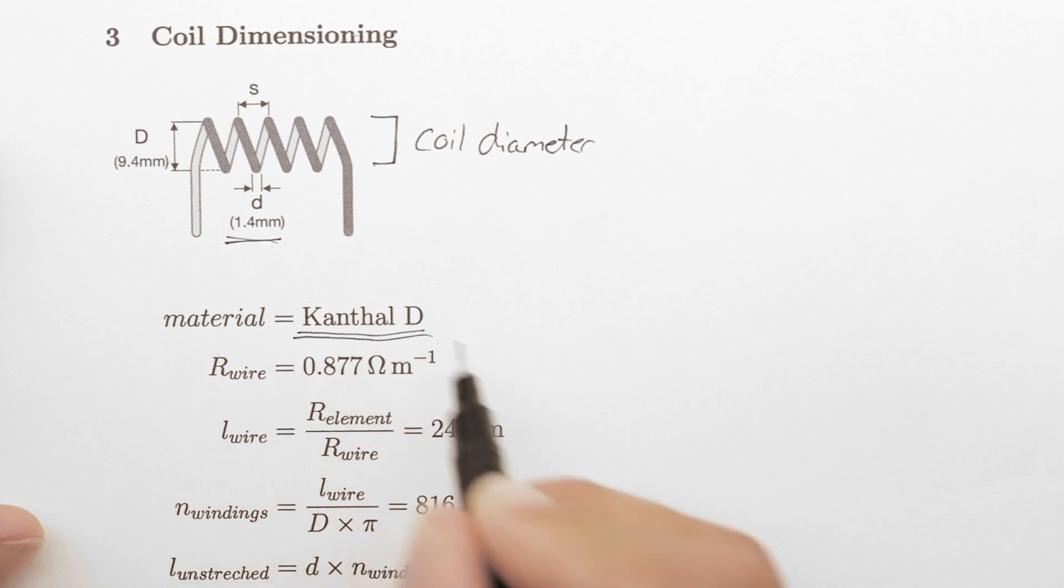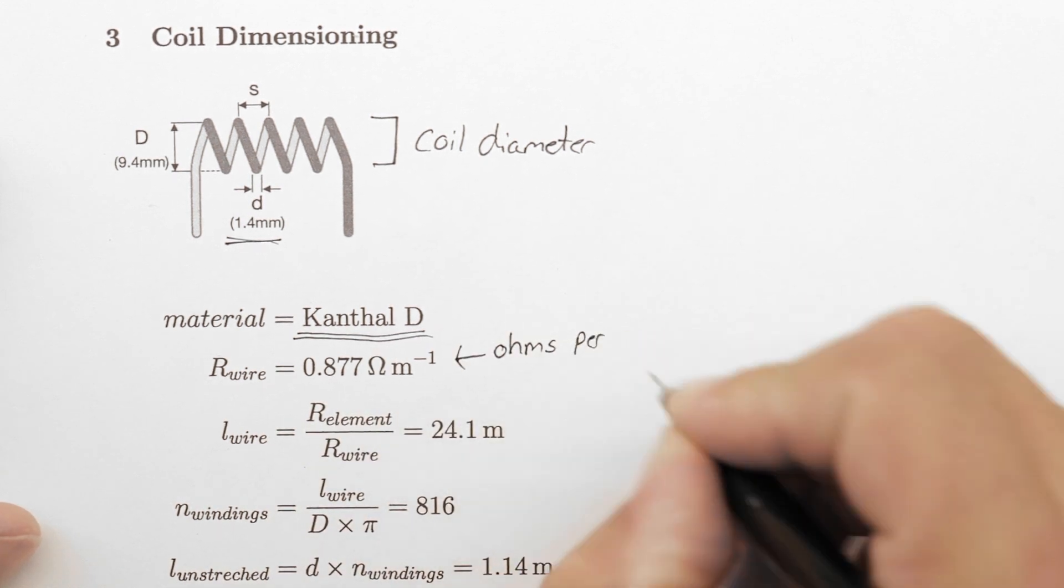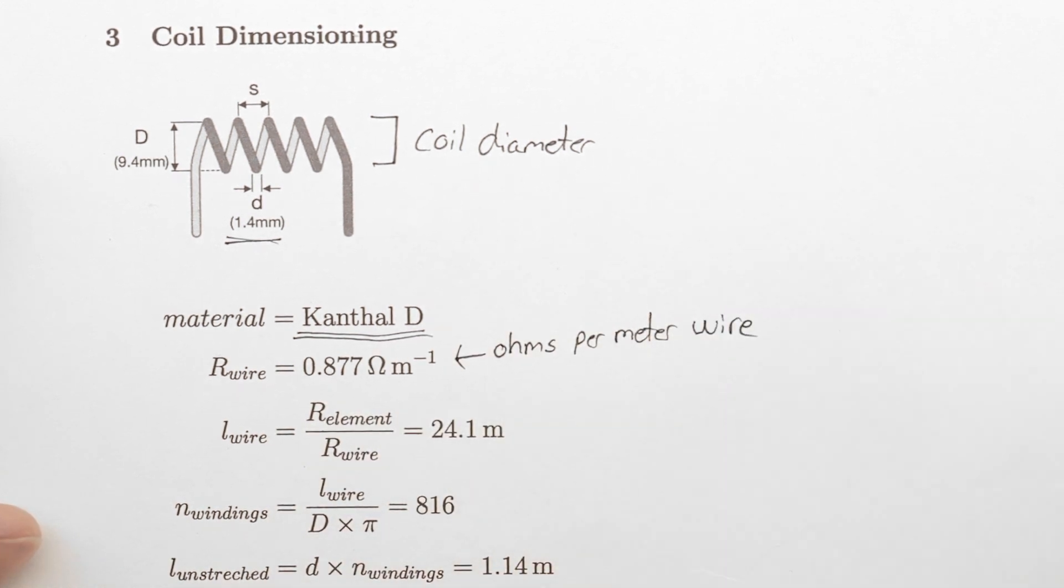According to its datasheet, it has a resistance of 0.877 ohms per meter. The required length of heating element wire is determined by dividing the desired resistance by the resistance per meter. This gives us 24.1 meters.